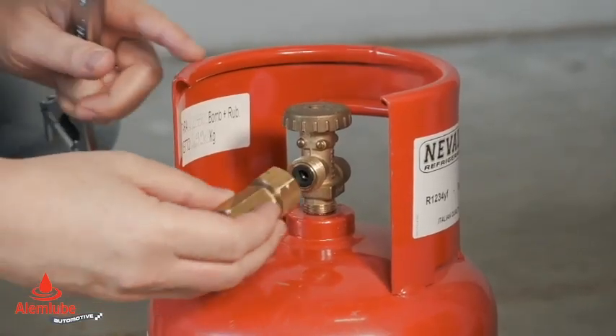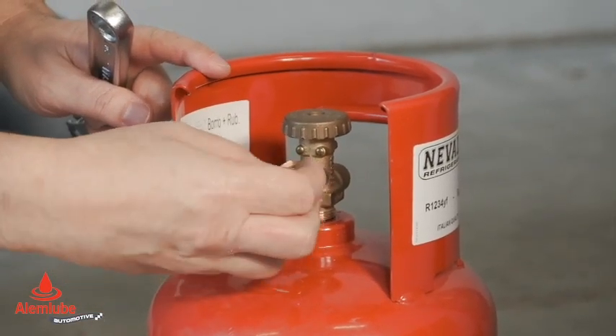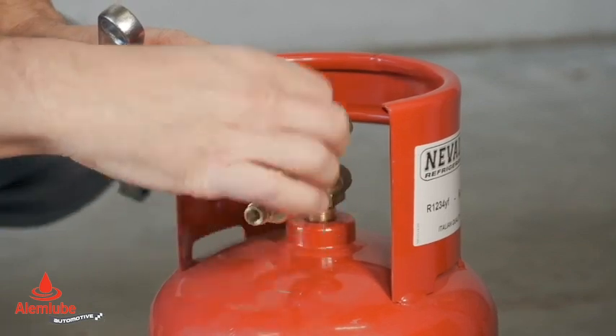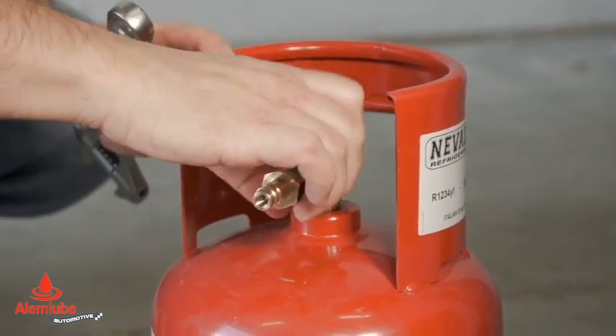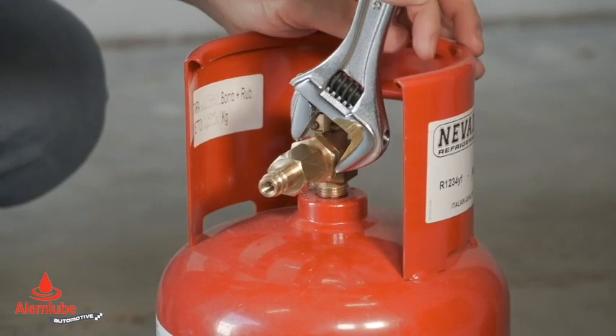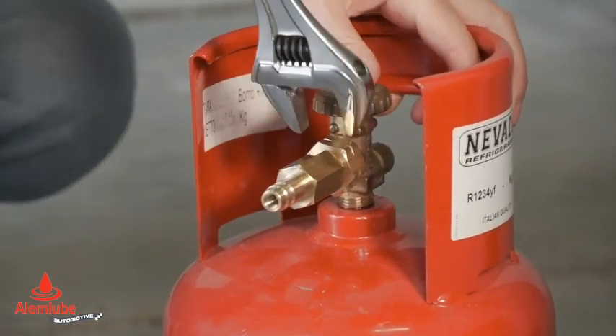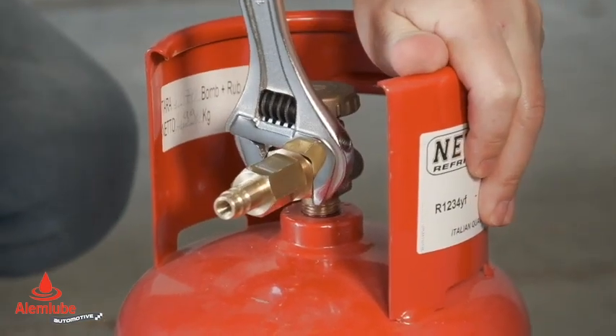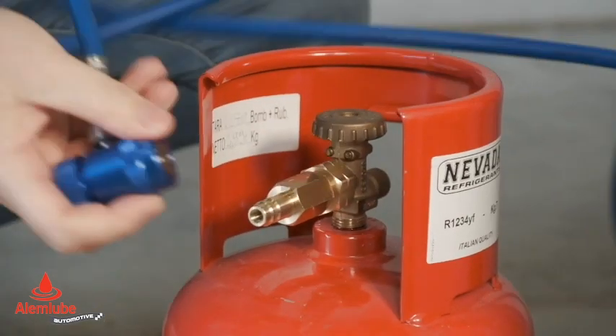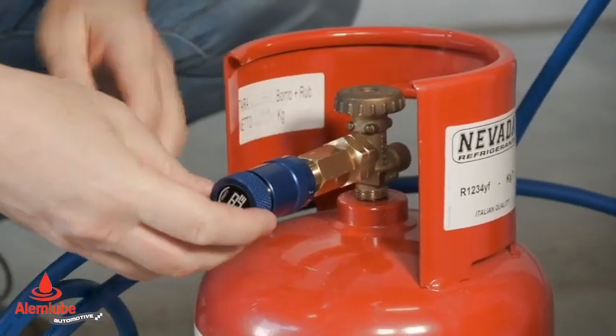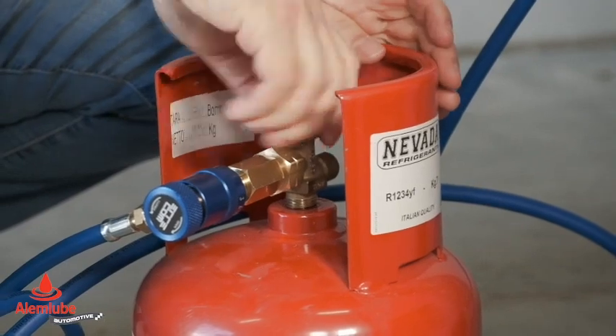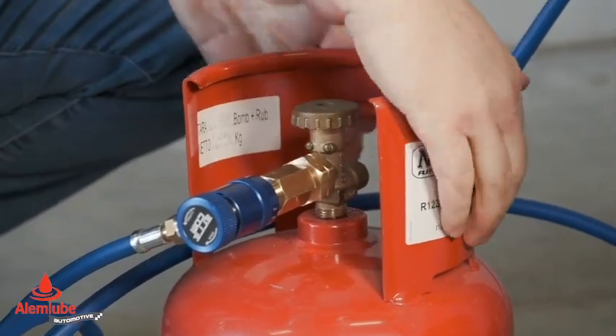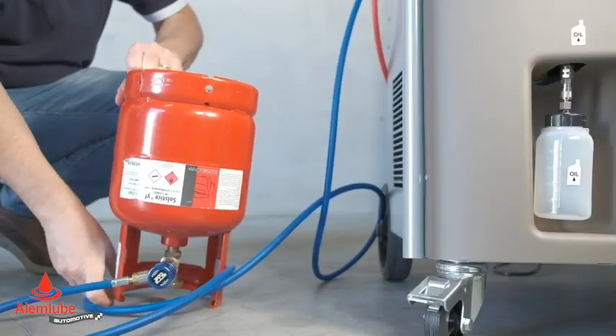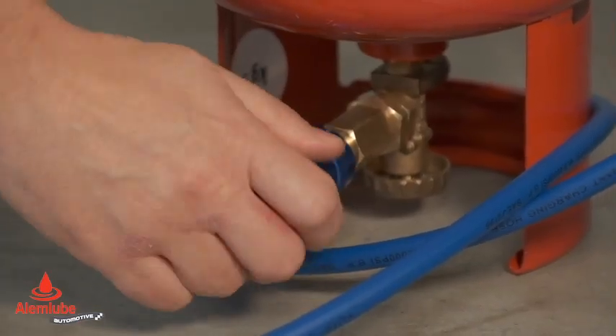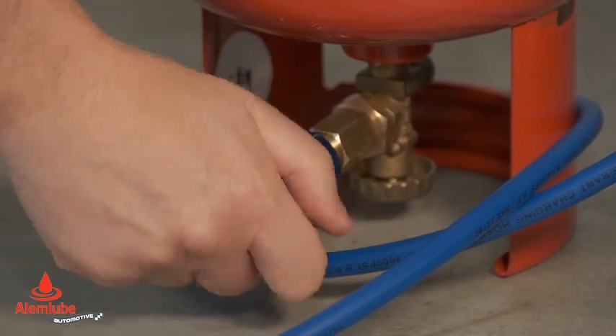Connect the adapter fitting to the cylinder and tighten well. Connect the service hose to the cylinder fitting. Turn the cylinder upside down to recover the refrigerant in the liquid phase. Open the tap to prepare for filling the equipment's internal cylinder.